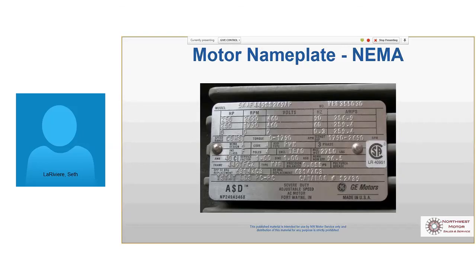So this is just a look at a GE nameplate. We talked earlier about the adjustable speed drive rated motors. This is one of those, and I can tell because when I look at it here, it's got the horsepower. This is the motor's nominal RPM, 1800. This one can be overspeeded to 90 hertz. So it's got a 90 hertz, there's the 2700 RPM, and the amps at that, and then the amps at 1800 at 60 hertz, and then the amps and horsepower at 0 speed. So you've got data all the way across the speed range of this motor.